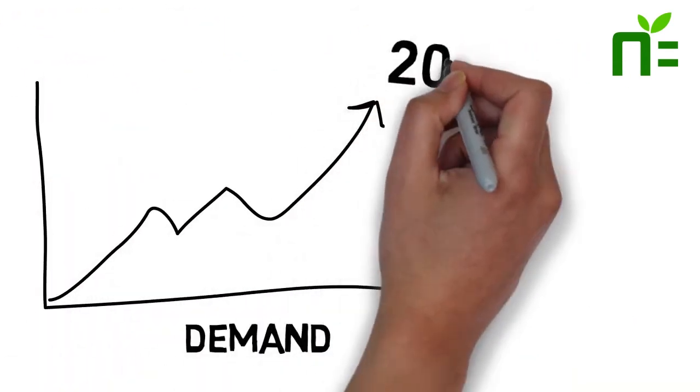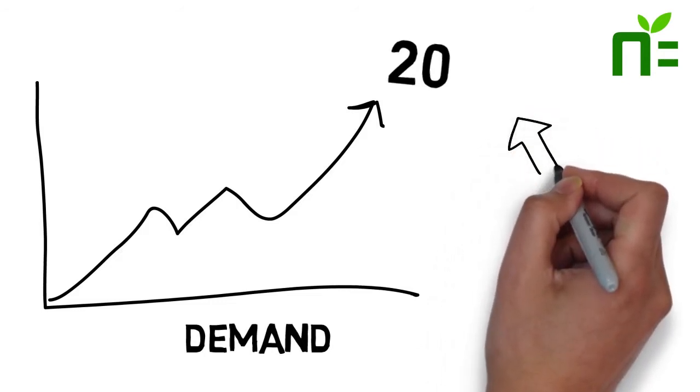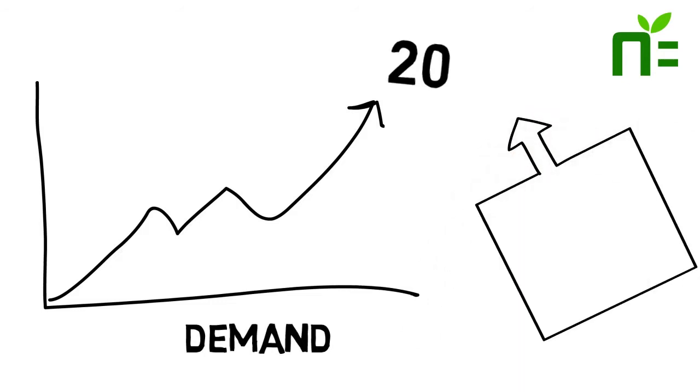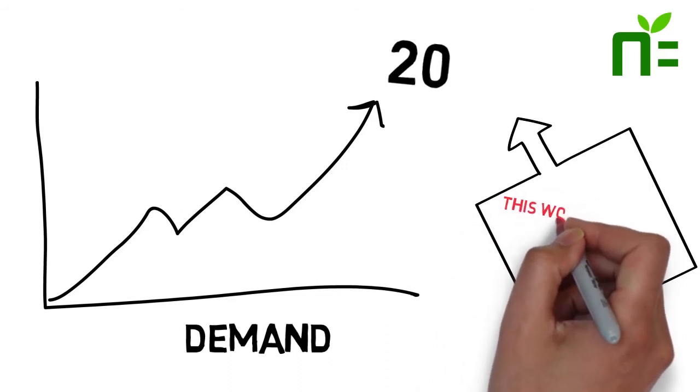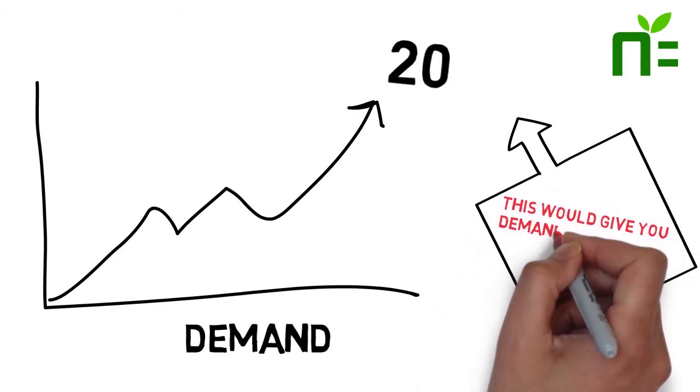Even though your average use is 10 or sometimes 5, the fact that you used energy at a rate of 20 kilowatts in one half-hour period would give you a demand charge of 20.